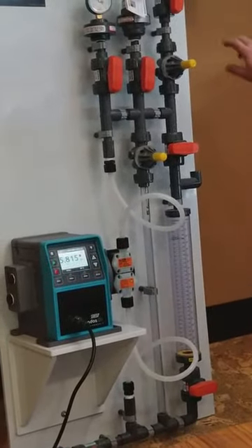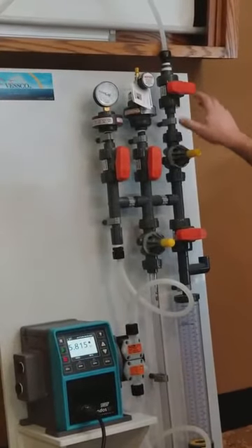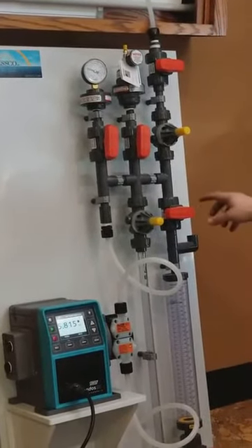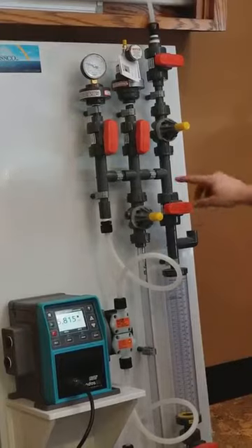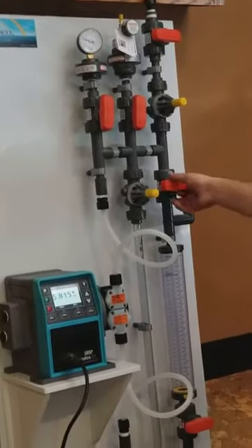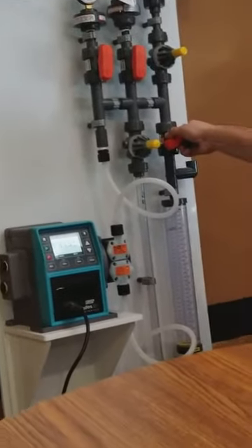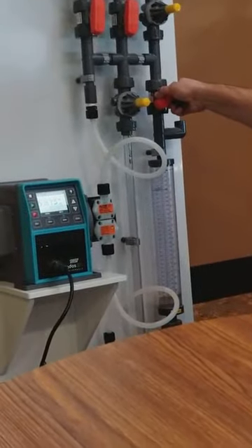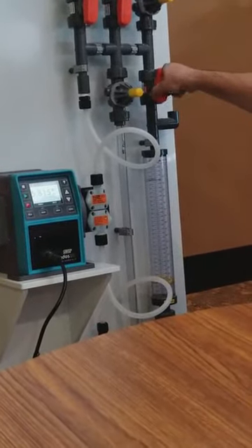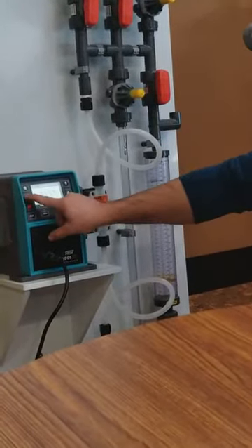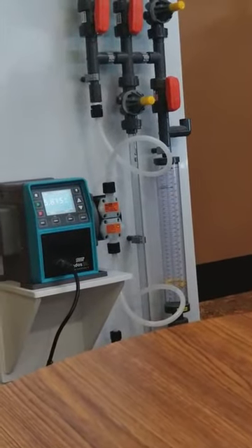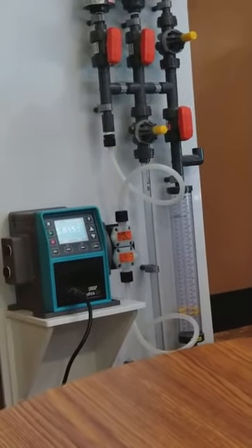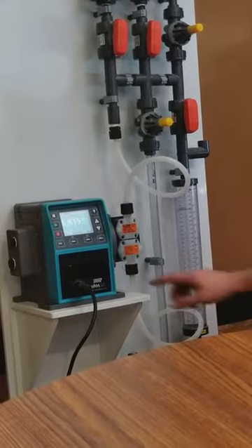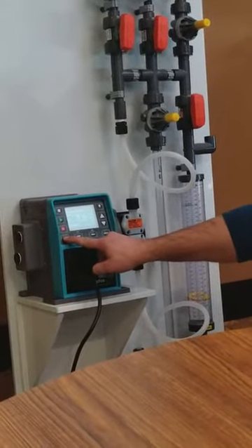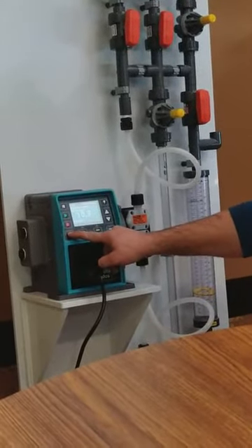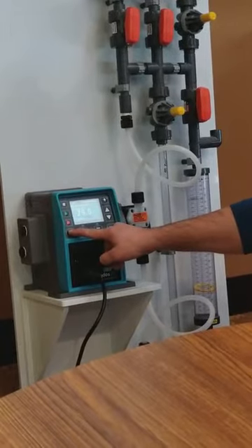So in order to do that, we're going to close our discharge. For this particular setup that we've got here, you can either pour liquid into it or we can actually feed through and fill our calibration column. So we'll go ahead and open up our filling valve for the calibration column. Go ahead and start running the pump. Also, there's this nice feature for max button, so we can max this pump out and speed the process up.